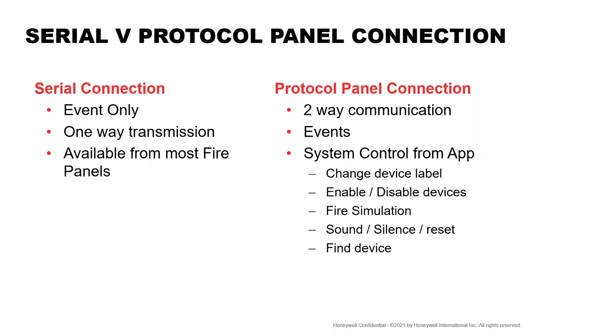Interestingly, you can also do fire simulation. This is really important for cause and effects testing, because on bigger buildings, we tend to have a complicated cause and effects, mainly to control evacuation, because it's all well and good an event coming into a fire system. If you just ring in every bell, ring all the bells, and everybody tries to get out as quickly as they can, you just move the risk, basically, from it being a fire risk to then a crush risk from everybody trying to pile down the stairs. So fire simulation to control the cause and effect, make sure the escape strategy works, is good.